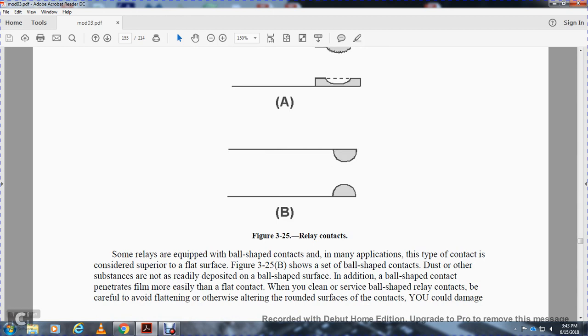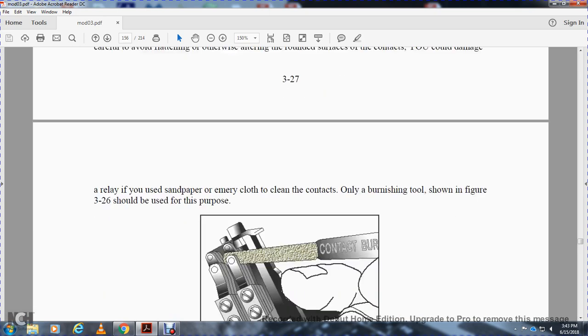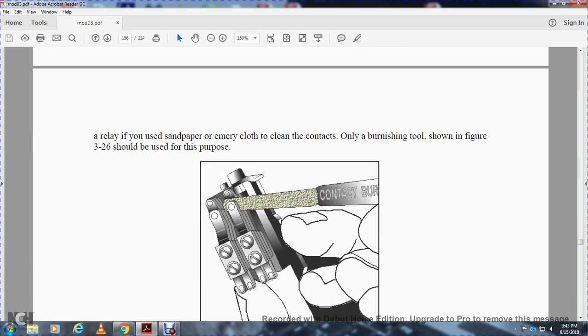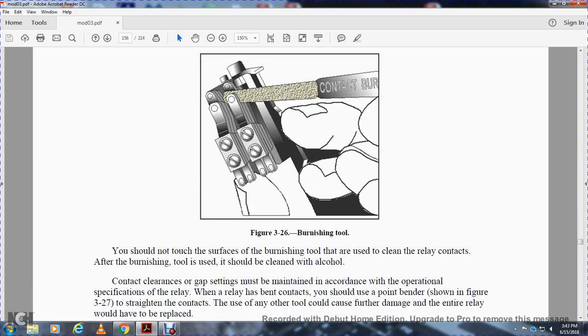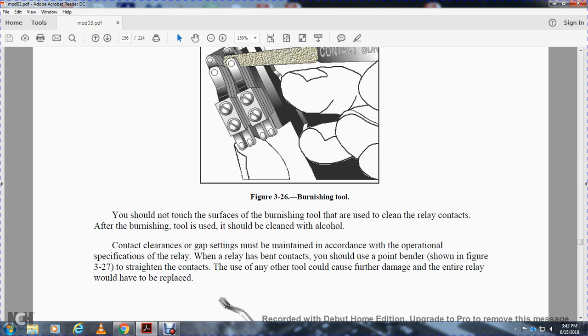In addition, ball-shaped contactors penetrate the film more easily than a flat contactor. When you clean or service ball-shaped relay contacts, be careful to avoid flattening or otherwise altering the rounded surfaces of the contact. You could damage a relay if you use sandpaper or cloth to clean the contacts. Only a burnishing tool, shown in Figure 3-26, should be used for this purpose. You should not touch the surface of the burnishing tool that is used to clean the relay contacts. After the burnishing tool is used, the contacts should be cleaned with alcohol.